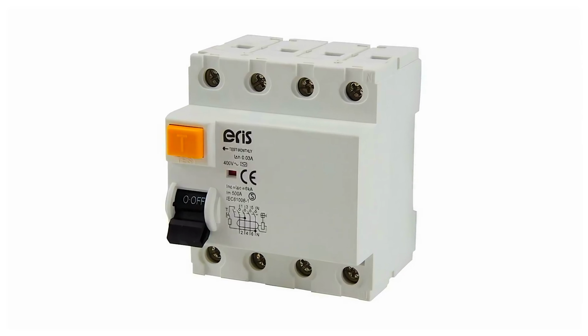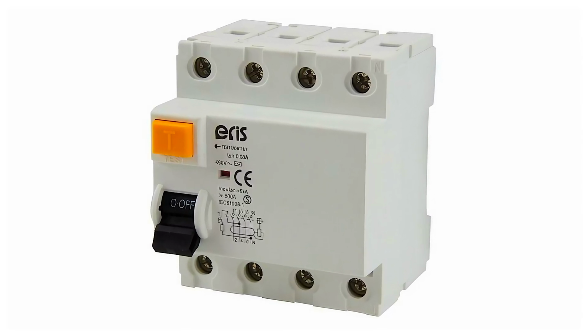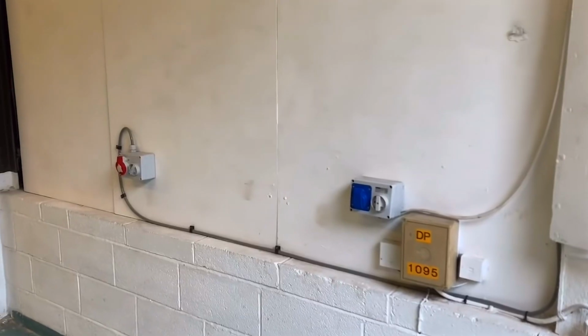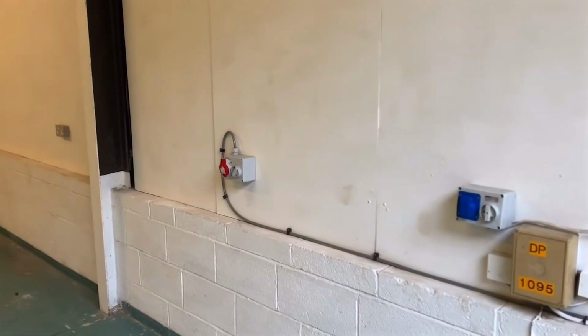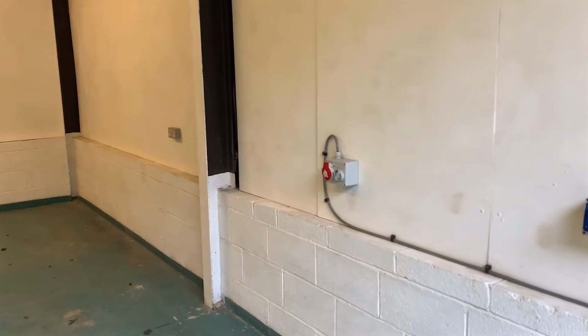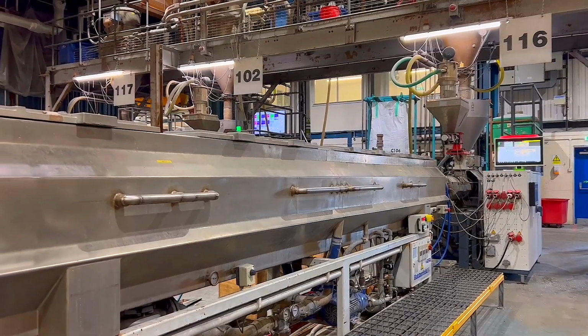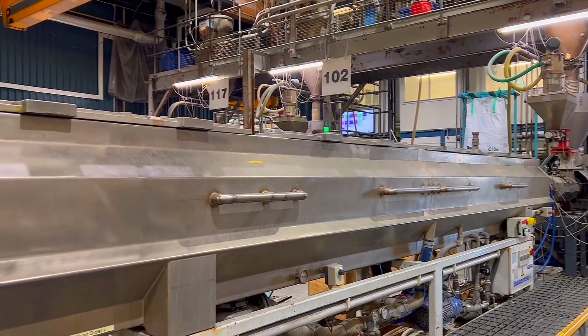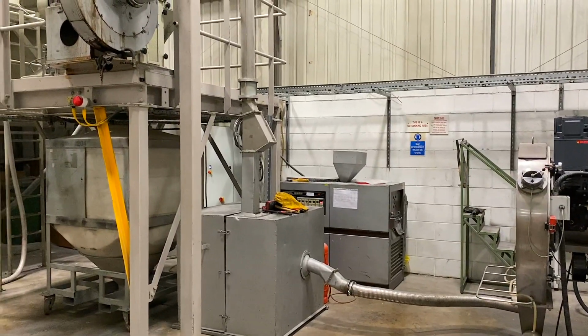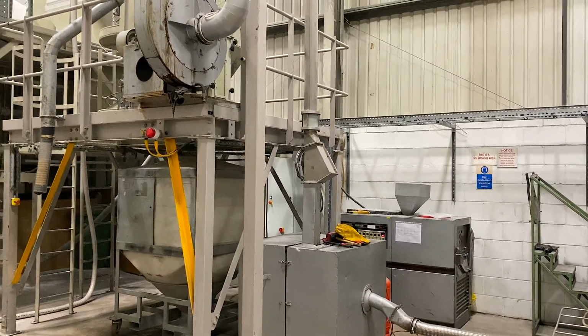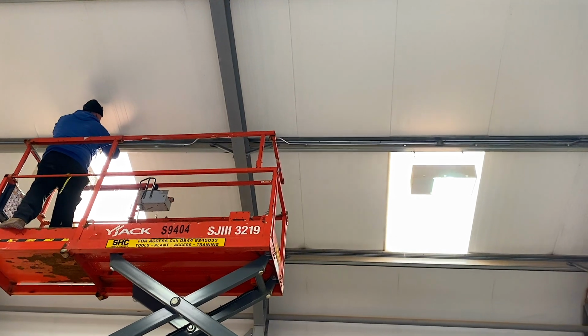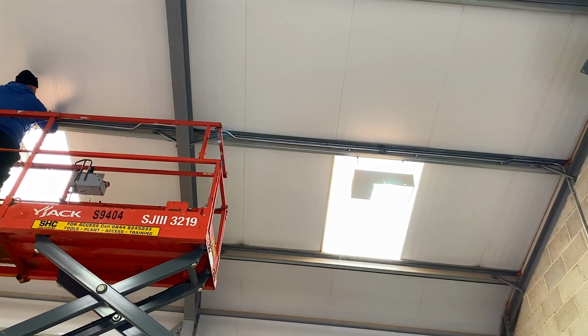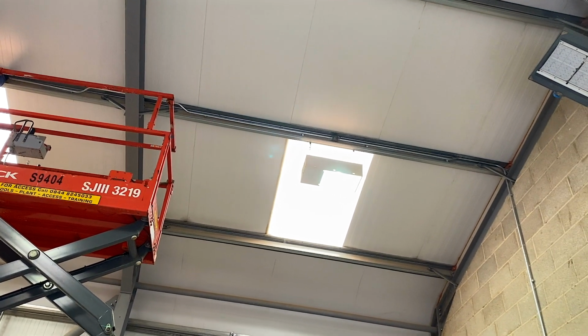RCBOs, residual current breaker with overcurrent, are often paired with MCBs, miniature circuit breakers, to provide enhanced protection for outgoing circuits, particularly for socket outlets rated at 32 amps or less. In industrial environments, however, MCBs are more commonly used. This is because industrial loads typically consist of fixed equipment like machinery, and the cabling methods often do not require additional protective measures. MCBs in these boards can handle ratings of up to 63 amps.